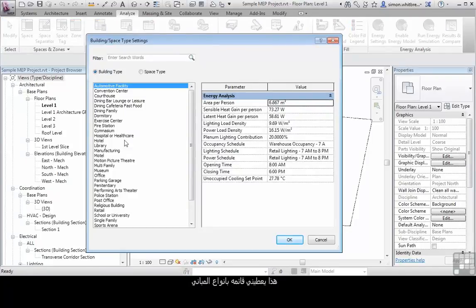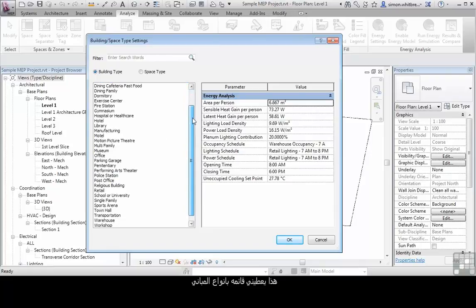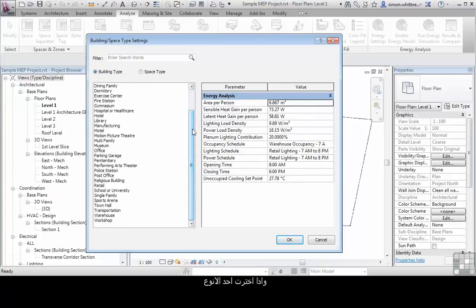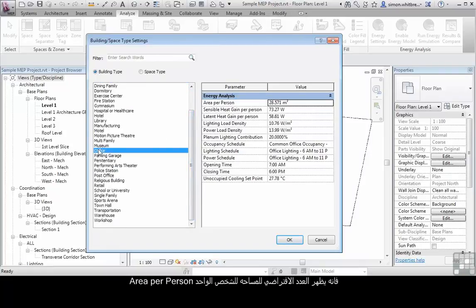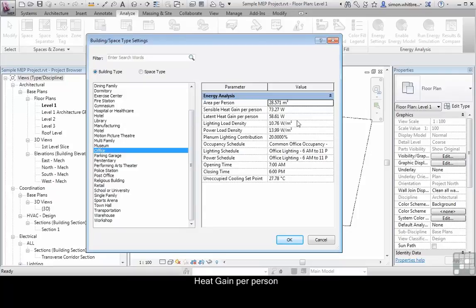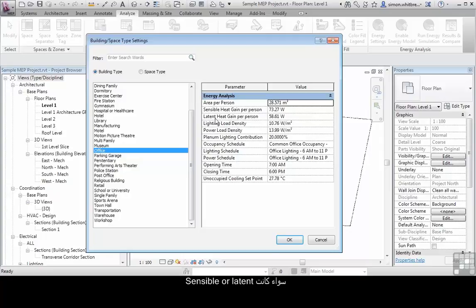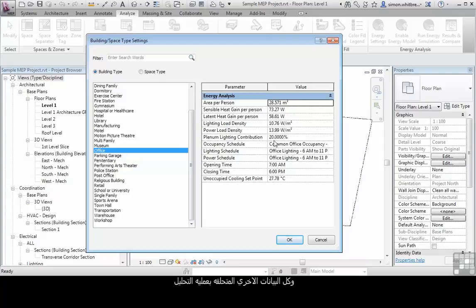This shows me a list of building types, and if I select one it shows the default area per person, heat gain, whether sensible or latent, lighting load density, power load density, and all the other data fields associated with building analysis.